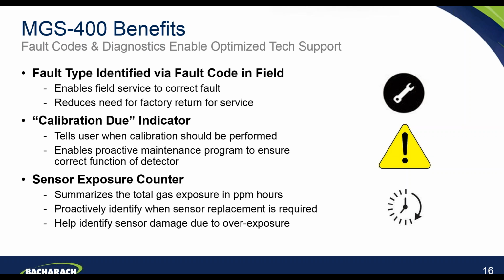Another feature that we have in there is a sensor exposure counter. So what this does is essentially summarize the total gas that sensor has been exposed to in its lifetime in terms of ppm hours. So what this does again is it enables the engineers, the service company, the end user to proactively identify when the sensor replacement may be required. And it also helps to identify if a sensor has been damaged due to, for example, a huge overexposure of refrigerant.